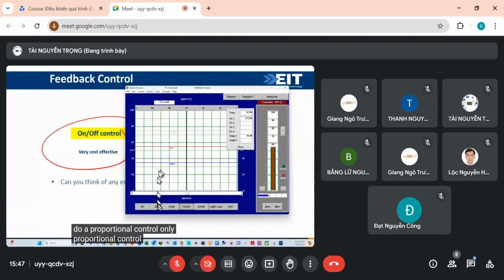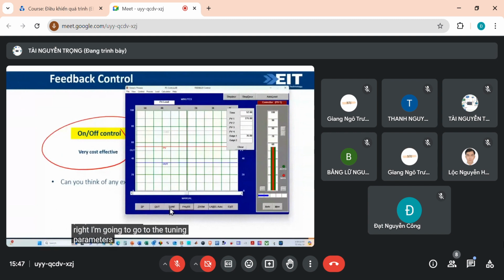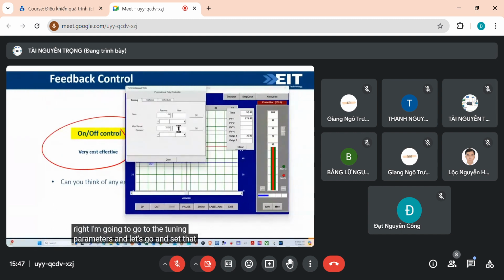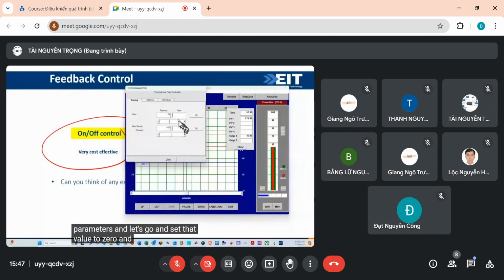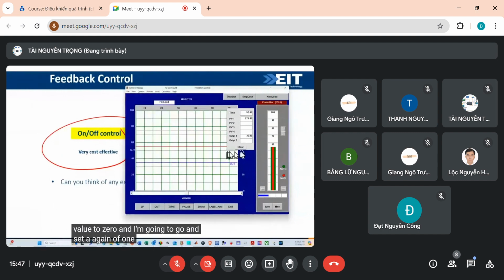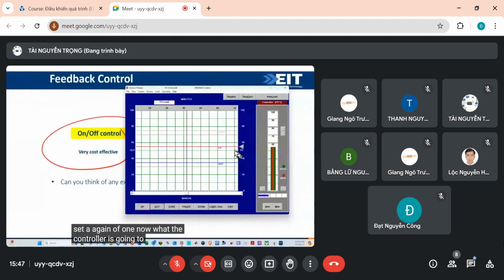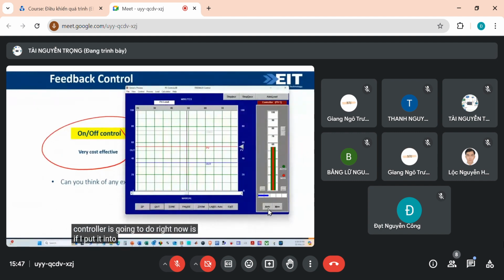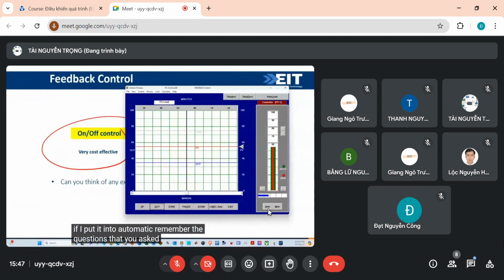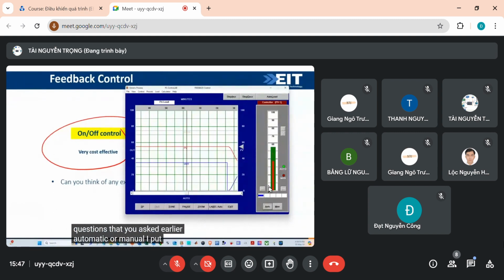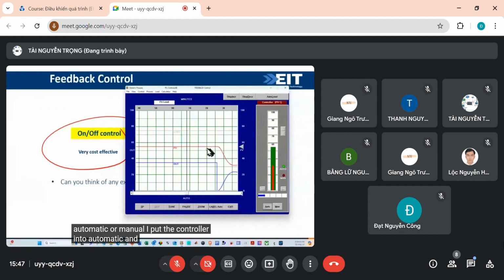Proportional control: I'm going to go to the tuning parameters and set that value to 0, and set a gain of 1. Now if I put the controller into automatic, remember the earlier question about automatic or manual, look what's happened.